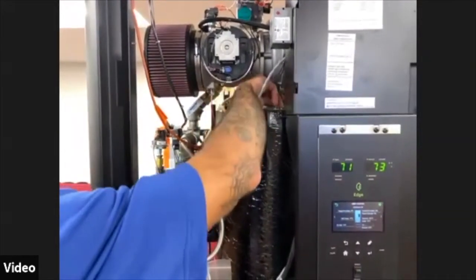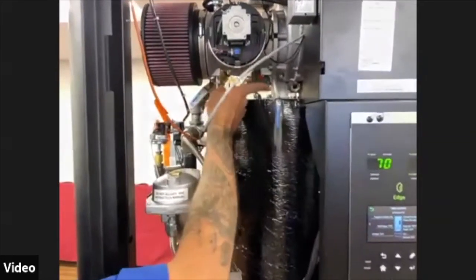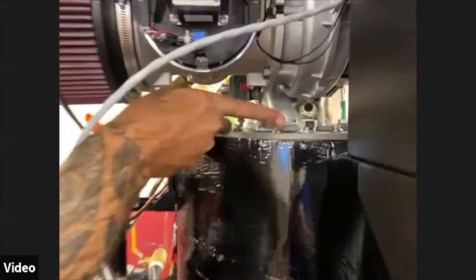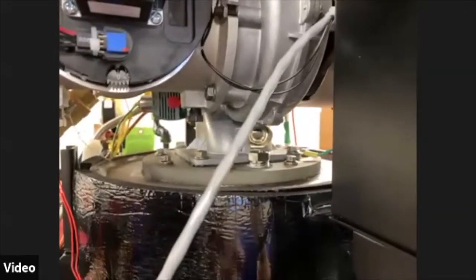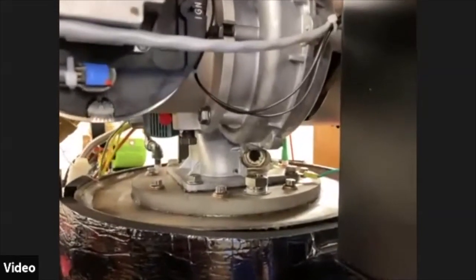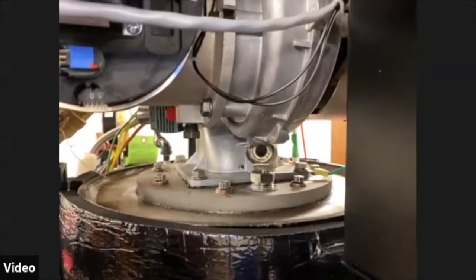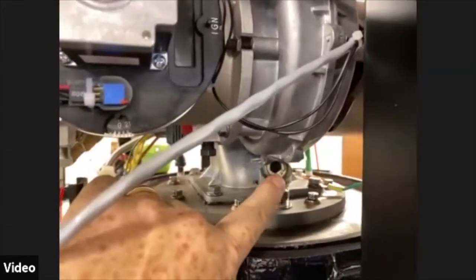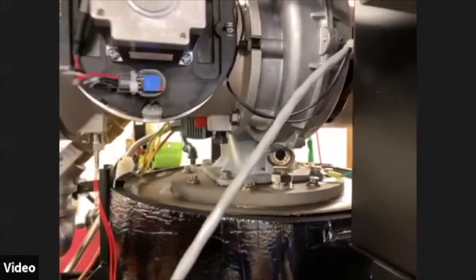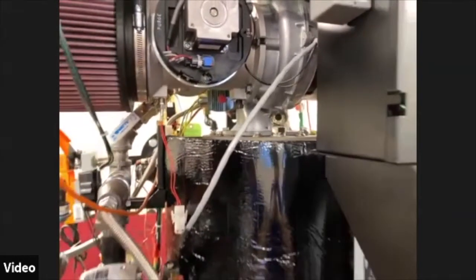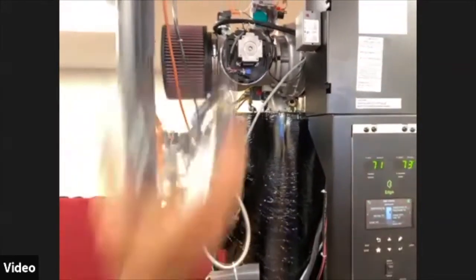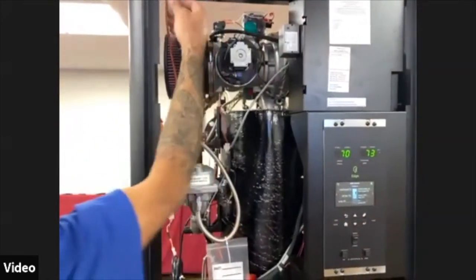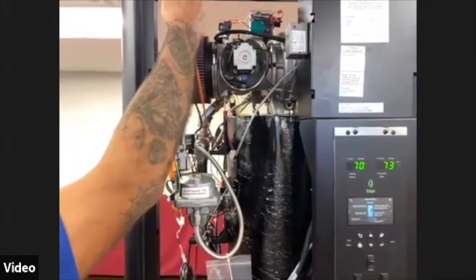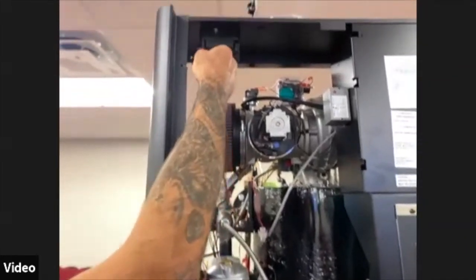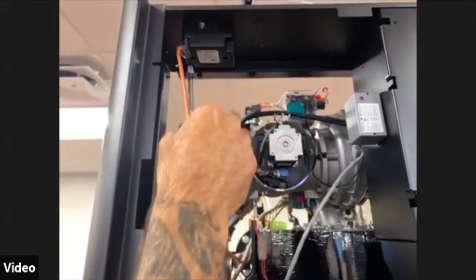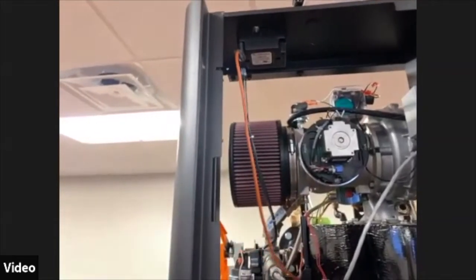Also up here on the top, you can probably see this little mirror here and this little sight glass. That's there so you can actually see the flame presence. When the boiler does ignite, you're able to see what that flame looks like and prove that you have flame up there. Ignition transformer is located right here on the top railing of the boiler. From there, we have our SSOV.